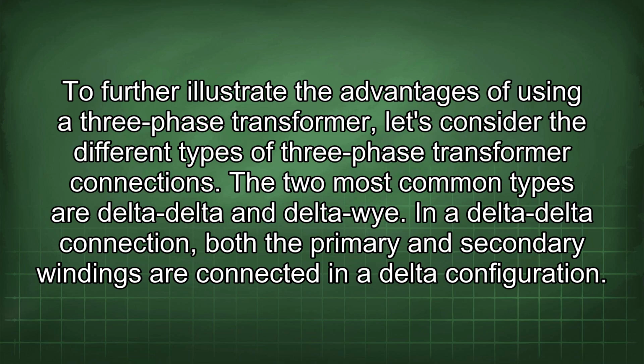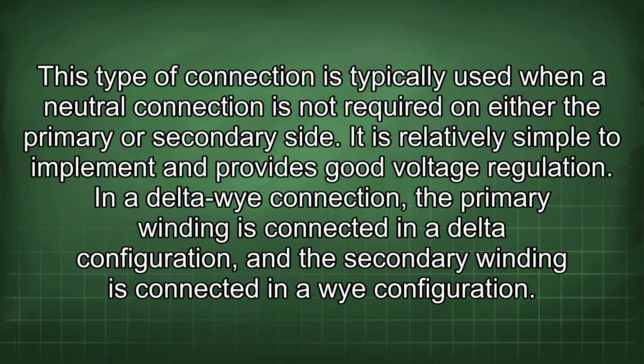The two most common types are delta-delta and delta-Y. In a delta-delta connection, both the primary and secondary windings are connected in a delta configuration. This type of connection is typically used when a neutral connection is not required on either the primary or secondary side. It is relatively simple to implement and provides good voltage regulation.